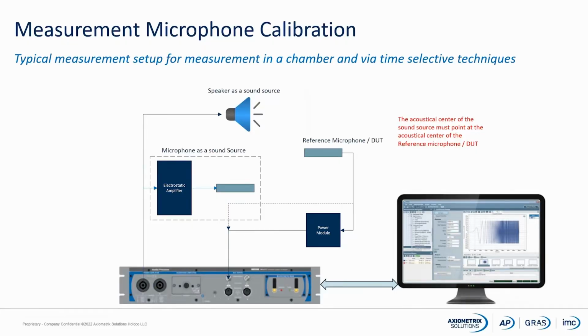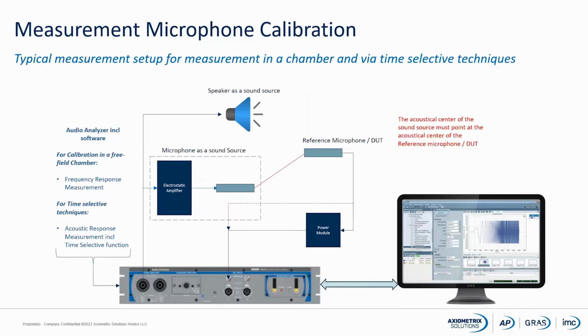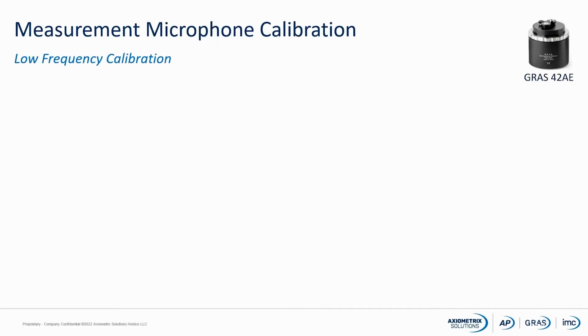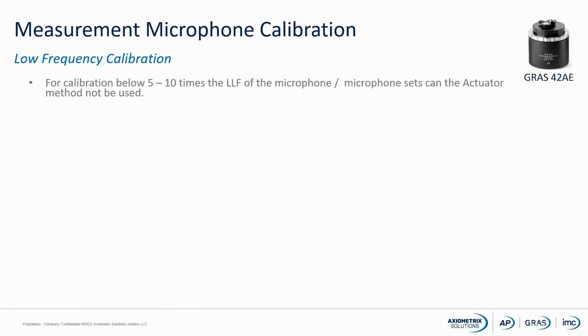Typical setup here for the time selective techniques. Our audio analyzer, for free field measurement in a free field chamber, frequency response measurement. For the time selective techniques, acoustical response measurements, including time selective functions. Low frequency calibrations. As mentioned before, if we would like to measure and calibrate the low frequency cutoff of a microphone, then we have some issues with the electrostatic methods, with the actuator methods, because we would measure wrong.